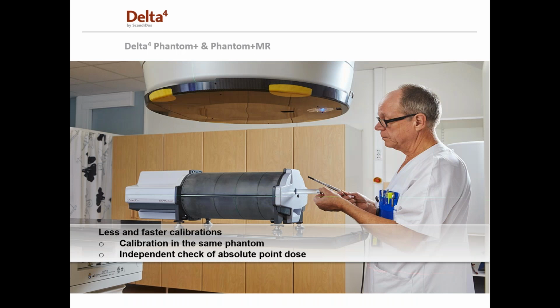Of course, you have to do the absolute dose calibration. What you see here, the gentleman is pulling the ion chamber insert out of the Phantom. You tell us what kind of ion chamber you're going to use for your absolute dose calibration, and we include that ion chamber insert. Some sites will purchase multiple ion chamber inserts. For example, they may want to use a Farmer chamber to do their absolute dose calibration, but during their actual patient QA, they may want to put a pinpoint chamber in so you can have an independent check of that point dose.